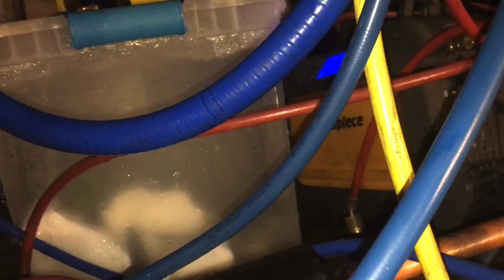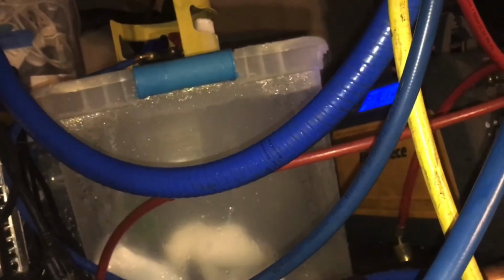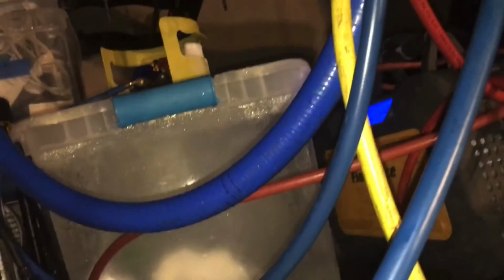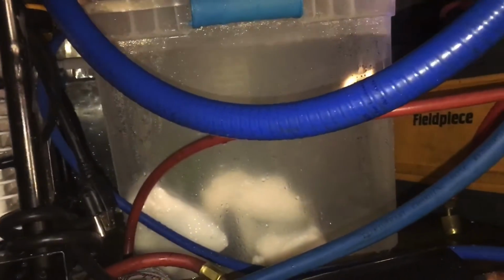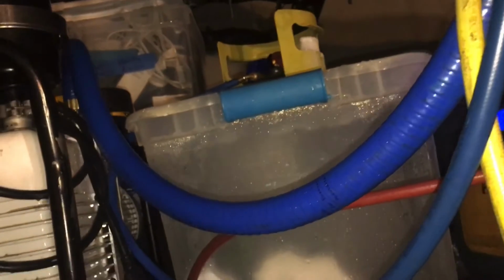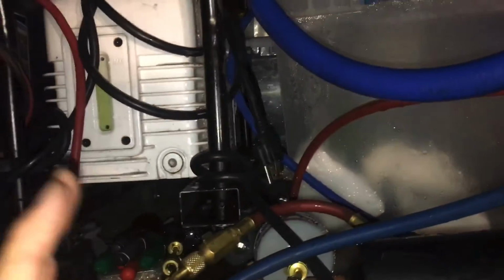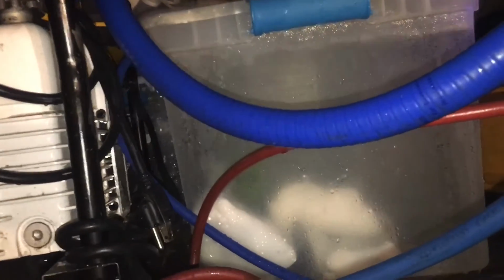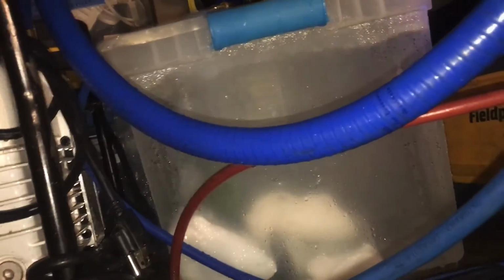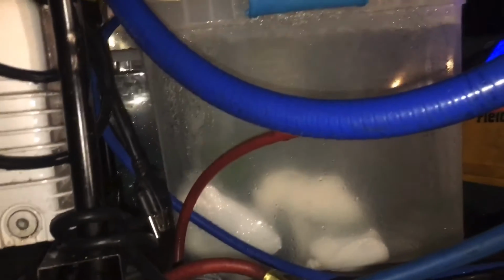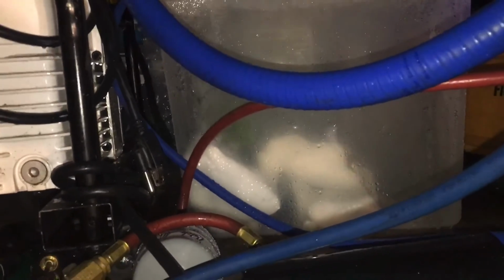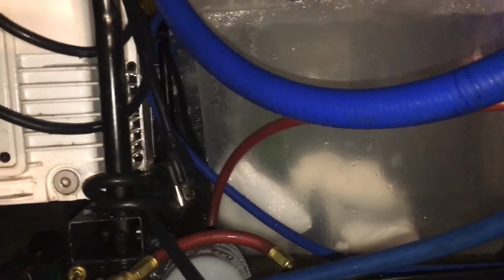where he thought they should be, because he is a technician who works on refrigeration, and he works at places like Safeway and big chain stores, and that's his job. He's done, I would guarantee he probably has 20 more years experience than I do at doing that kind of work. But when it comes to VRF, the variable refrigerant flow systems, he definitely has zero knowledge. If the first thing you do is you come out to a system and start pumping in 20 pounds of refrigerant because you want to see some pressures, you're immediately fired from the job, never to be called back again. That is absolutely a no-no. So this guy just cost this customer, just in refrigerant recovery and recharge, a minimum of $1,000, probably a little bit more.